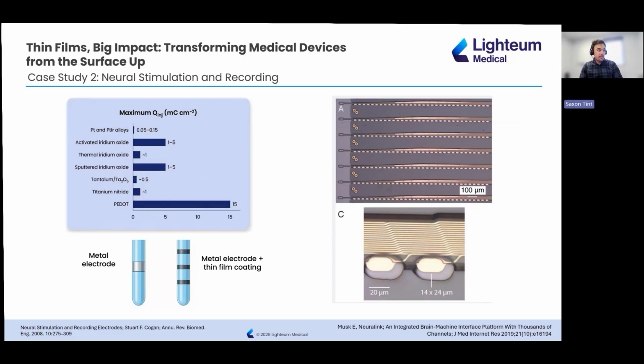This slide shows just how dramatic the effect of these coatings is. On the chart on the left, at the top, is charge injection capacity for different electrode materials. Bare platinum iridium coatings. Compare the bare platinum iridium to charge injection coatings like iridium oxide, titanium nitride, and especially PEDOT. The difference is not incremental, it's orders of magnitude. Higher charge injection capacity and lower impedance. They mean 2 things. First of all, for stimulation, we can safely pass enough charge into the tissue without damaging it, even from very small electrodes. Secondly, for recording, lower impedance directly reduces electrical noise and improves high frequency response. This means clean recordings of those tiny action potentials.